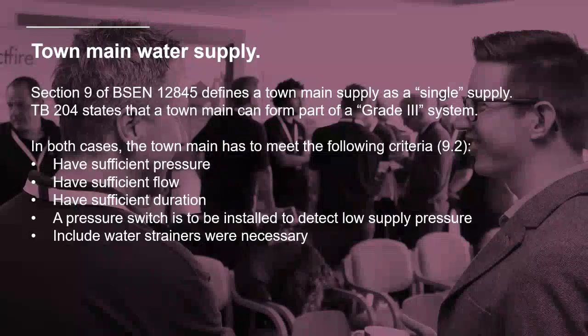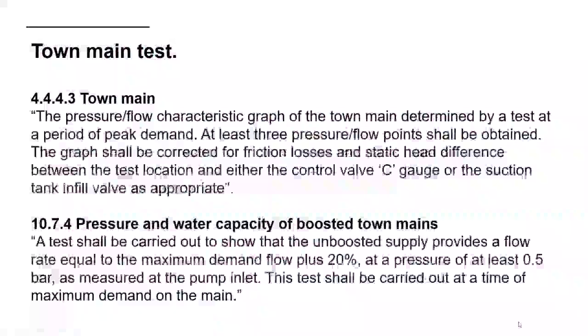There's a note about a pressure switch to be installed to detect low supply pressure. If pressure drops below a predetermined amount, then we get a warning. I guess it's a case of what we then do with that warning. There isn't a great deal that we can do, other than note that the alarm has come in. If it comes in and stays in, or appears every week for several months, then we've got a serious problem, and we need to contact the water authorities to see what can be done, or maybe decide that the town main is no longer of sufficient pressure to be deemed appropriate for the system. There's also a note to include water strainers where necessary. So, provided we can meet that, a town main supply is a good supply to use.